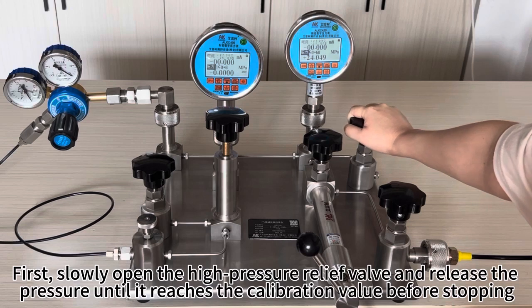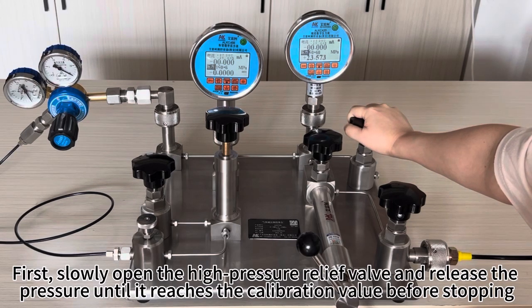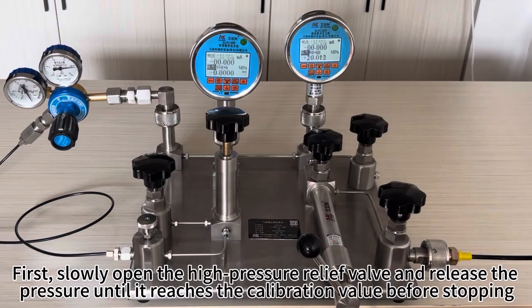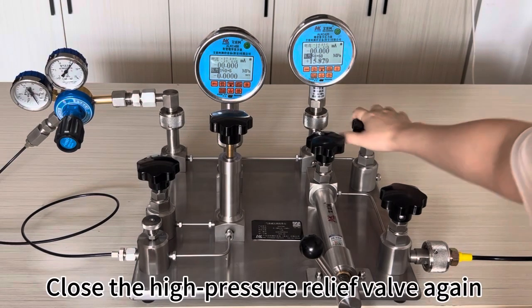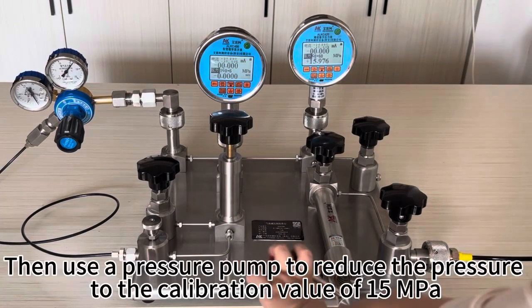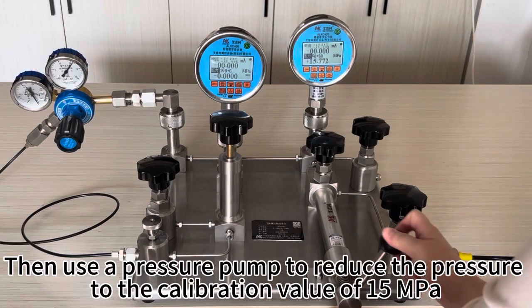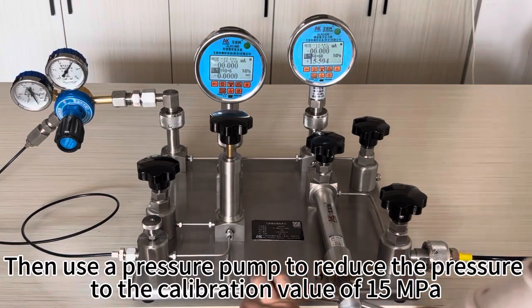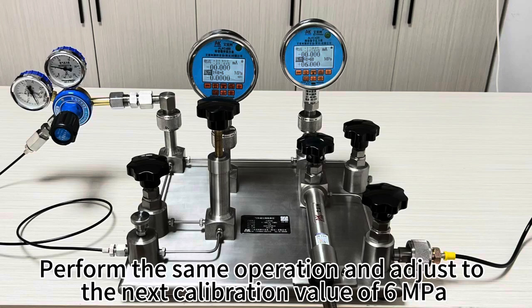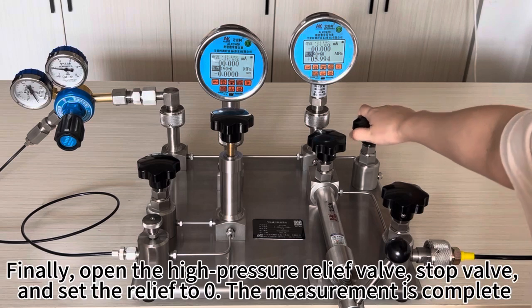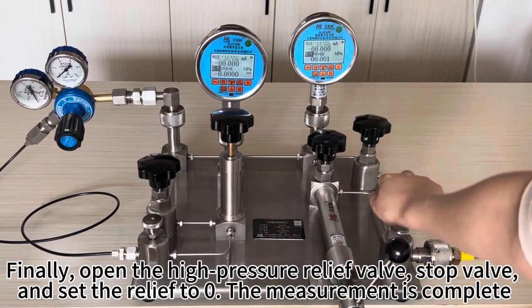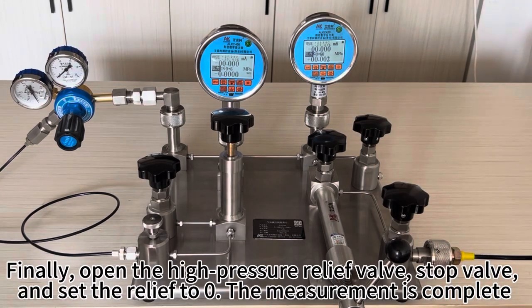First, slowly open the high-pressure relief valve and release the pressure until it reaches the calibration value before stopping. Close the high-pressure relief valve again. Then use a pressure pump to reduce the pressure to the calibration value of 15 MPa. Perform the same operation and adjust to the next calibration value of 6 MPa. Finally, open the high-pressure relief valve, stop valve, and set the relief to 0. The measurement is complete.